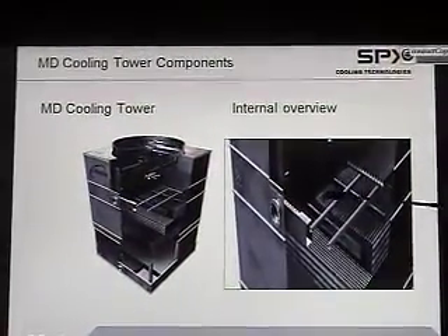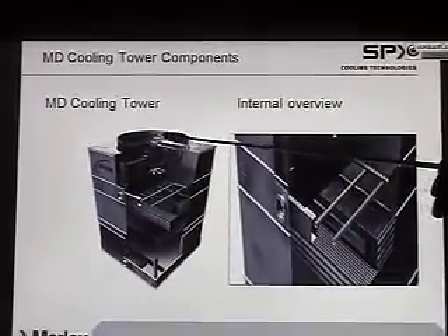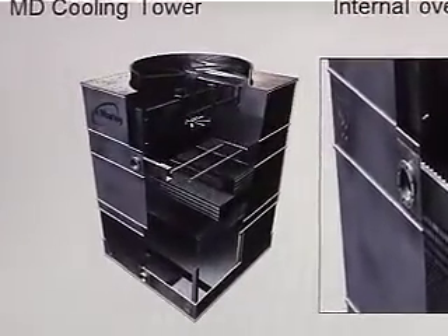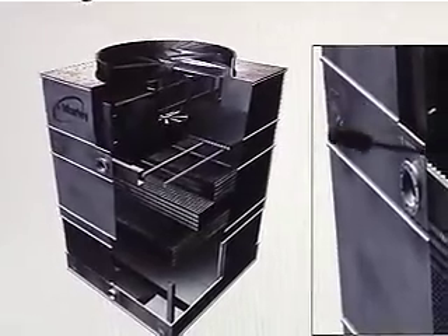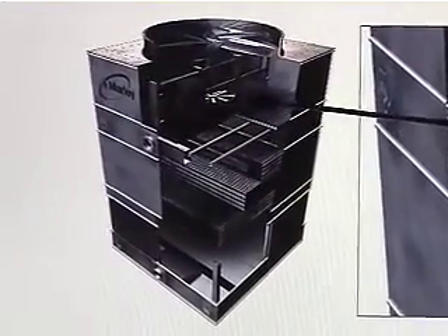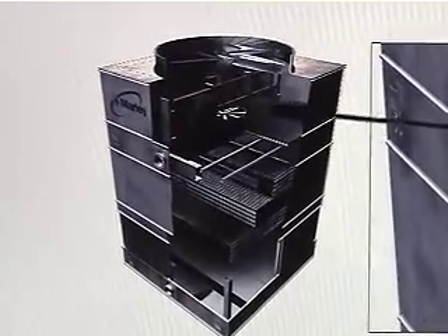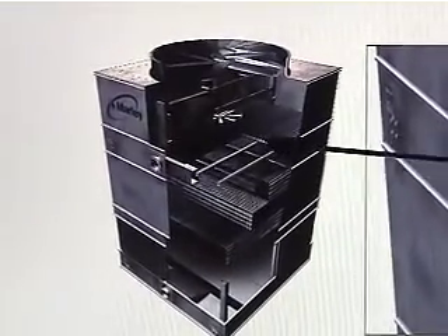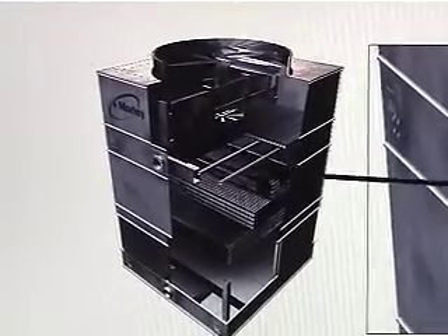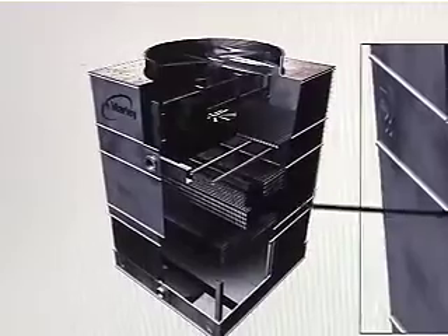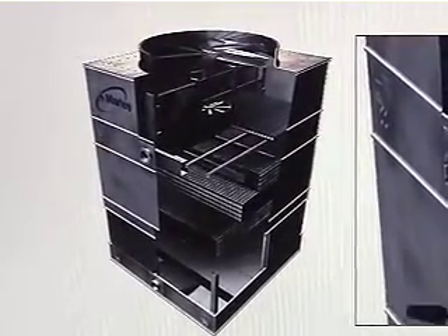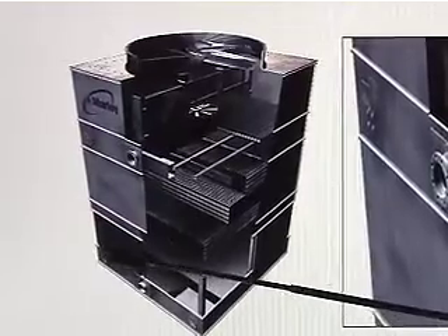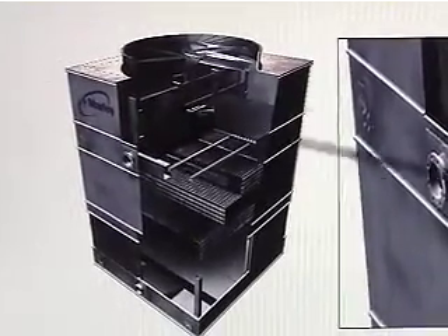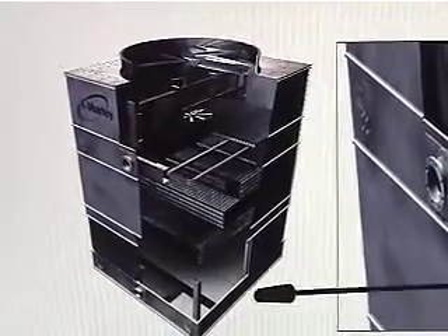Okay, these are the major components of the cooling tower that may need repair. Basically, this is your fan. Your motor is actually mounted outside, but this was the only picture that showed all the other items clearly. This right here is that about 4-inch thick drift eliminator. This is your spray system. This is the piping for it. This is the fill, the media which the water splashes over, and then the air comes in through these louvers over here on the side. The air comes in, and the water comes down, and it's a counterflow tower.